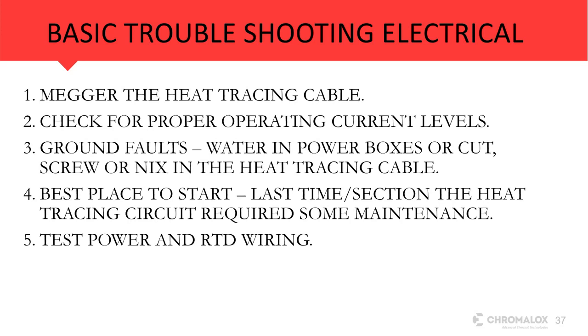One of the things that I like to tell people is that the best place to start is the last section of heat tracing circuit that required some maintenance. Typically, if we're going to have an issue, that's the best place to start. That's the last place we redid something, so that's typically where we might find some kind of issue. You can also test your power and RTD wiring if you get to the point where we've eliminated the other issues on the electrical side. Maybe we have some issues with the power that's run to the power box or the RTD wiring, so we can do a test on those.